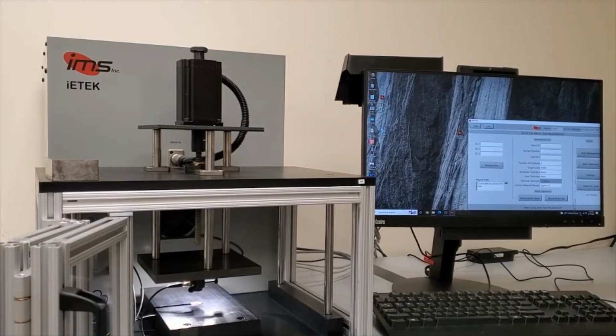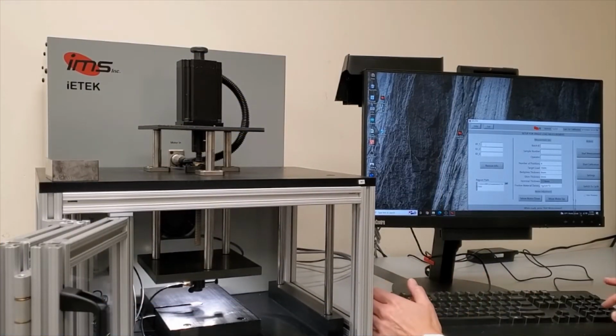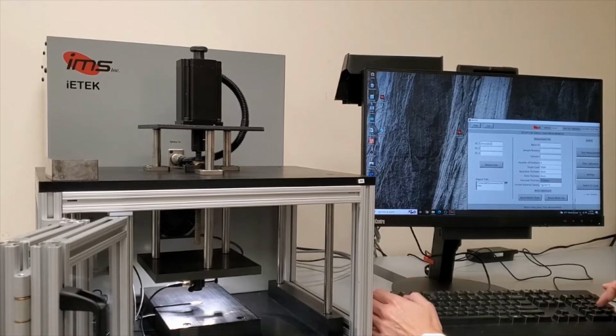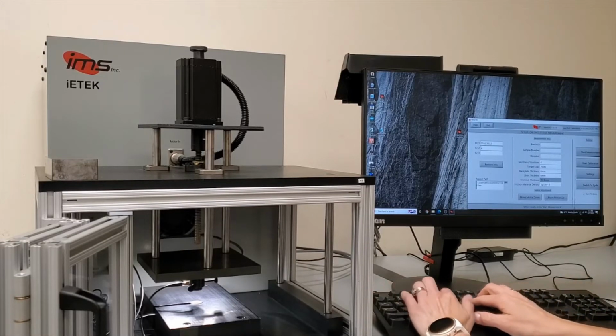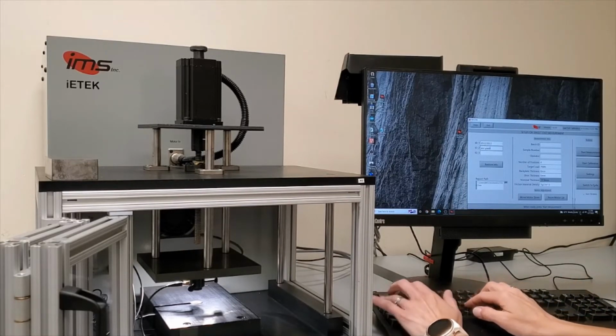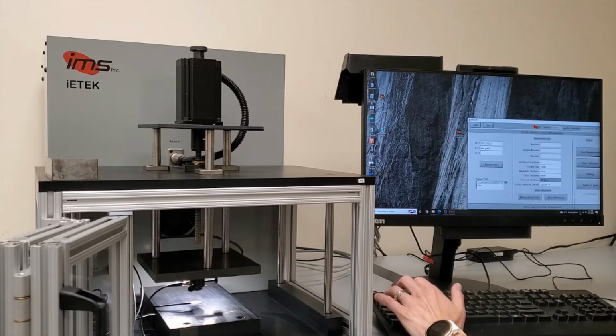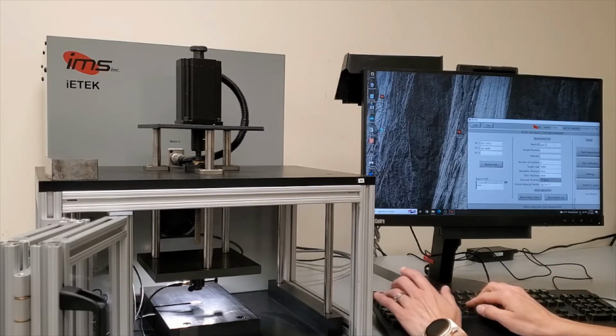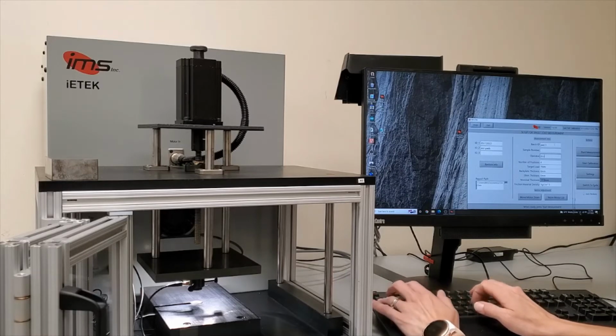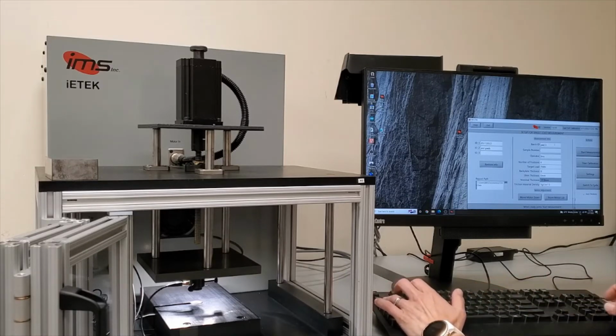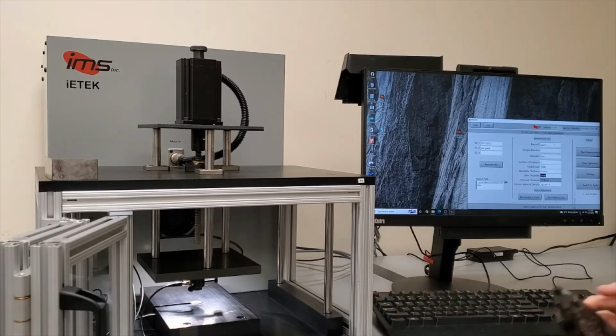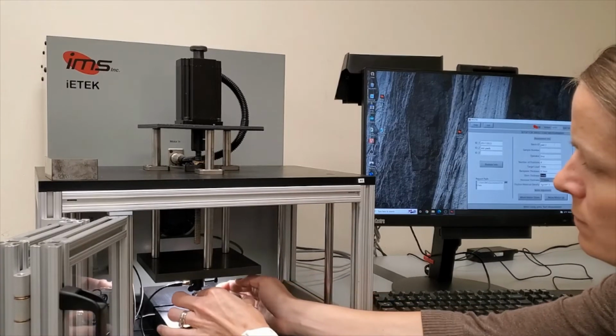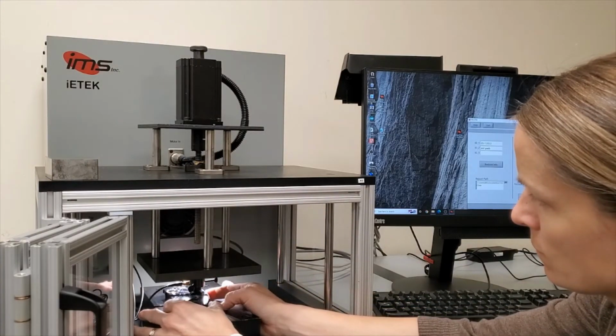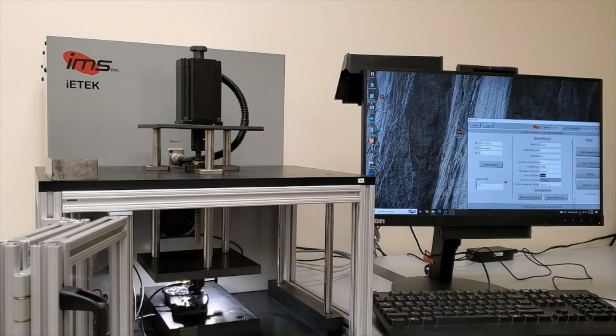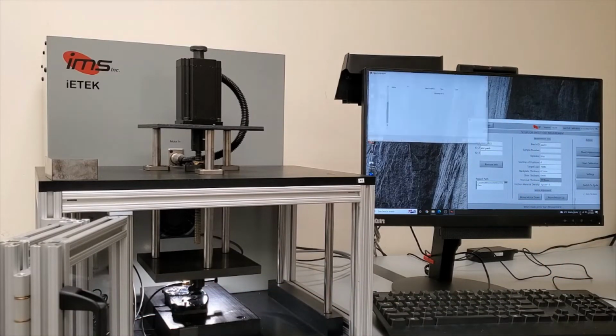To look at the measurement process, here we have the same setup. The pads will eventually find their way between the 2 transducers. The user is keying in some of the data in the user interface.